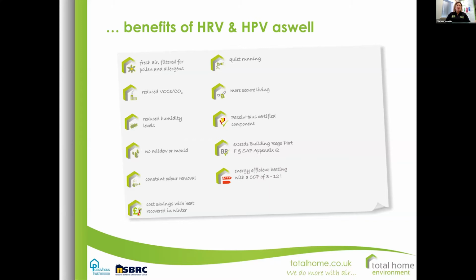If you have heat pump ventilation as well, you're going to get very energy efficient space heating. Now a COP of between 3 and 12 is really good. Just to explain, a COP is how much energy you put into something versus how much energy you get out. So it's a coefficient of performance.